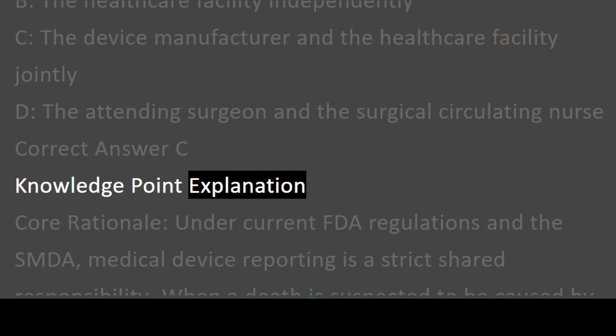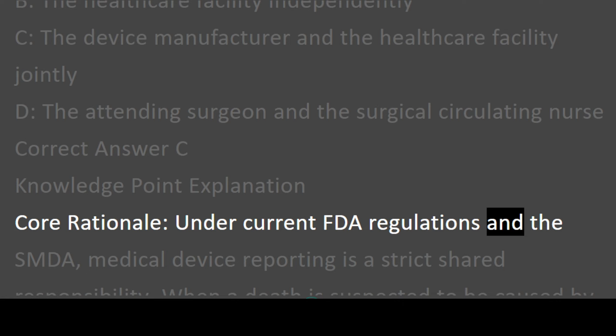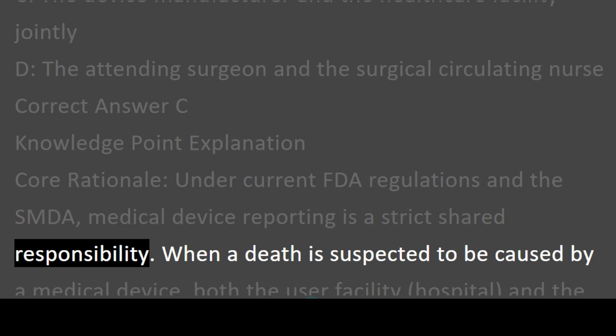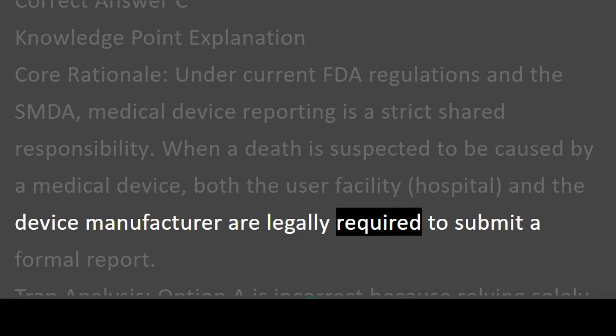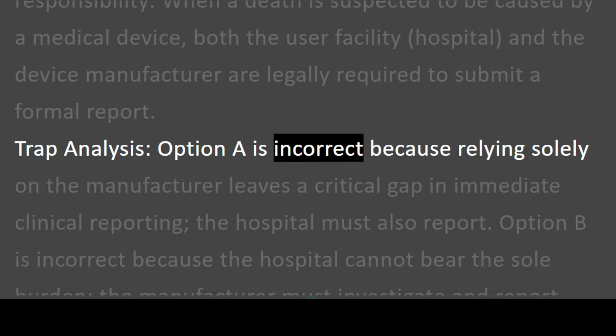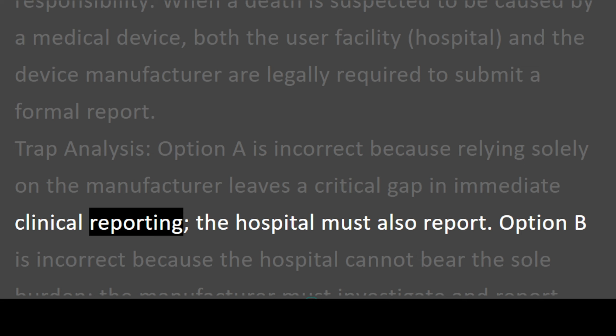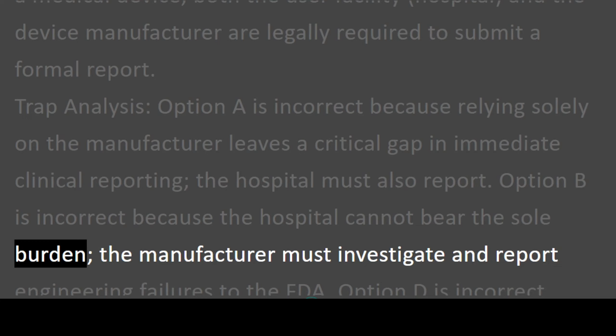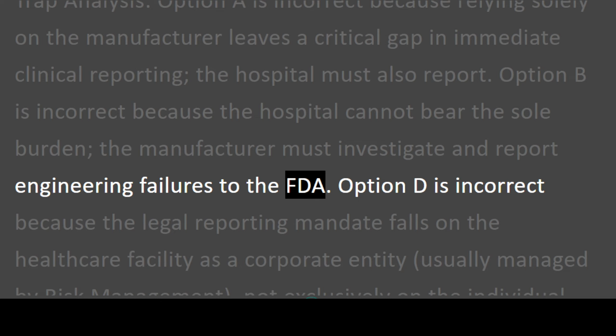Correct answer C. Knowledge point explanation. Core rationale. Under current FDA regulations and the SMDA, medical device reporting is a strict shared responsibility. When a death is suspected to be caused by a medical device, both the user facility, hospital, and the device manufacturer are legally required to submit a formal report. Trap analysis. Option A is incorrect because relying solely on the manufacturer leaves a critical gap in immediate clinical reporting. The hospital must also report. Option B is incorrect because the hospital cannot bear the sole burden. The manufacturer must investigate and report engineering failures to the FDA.